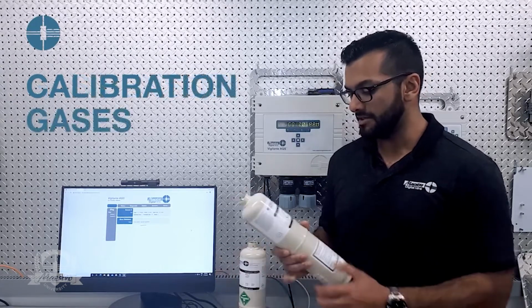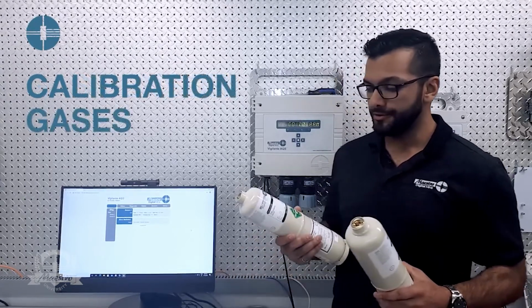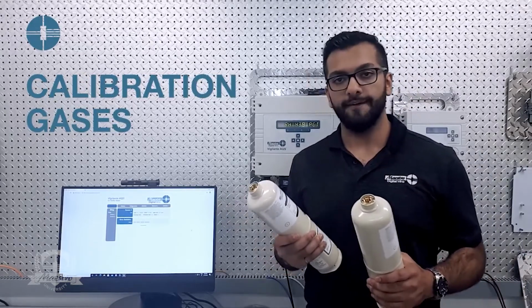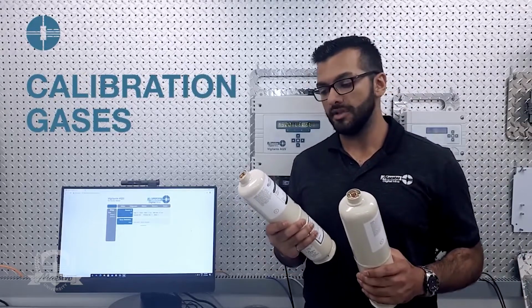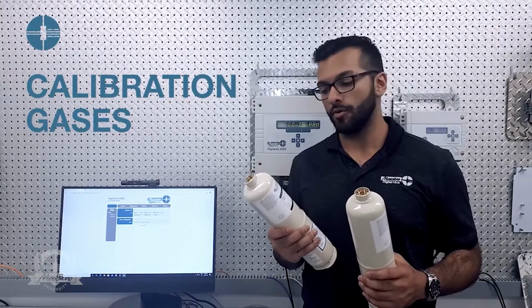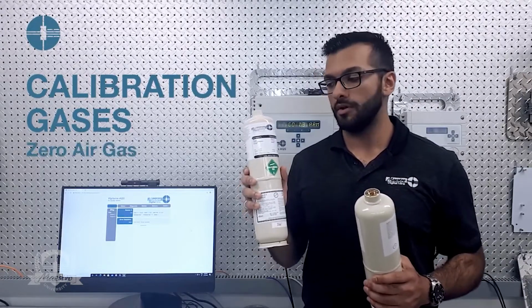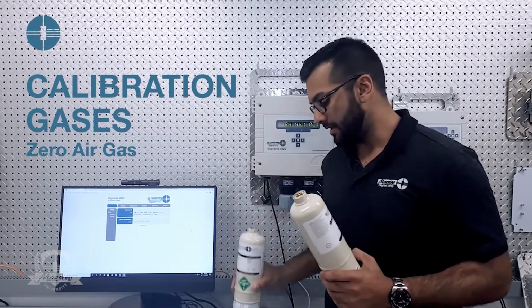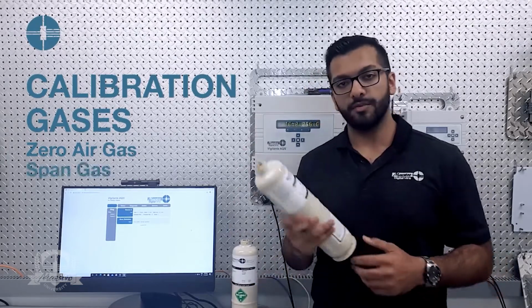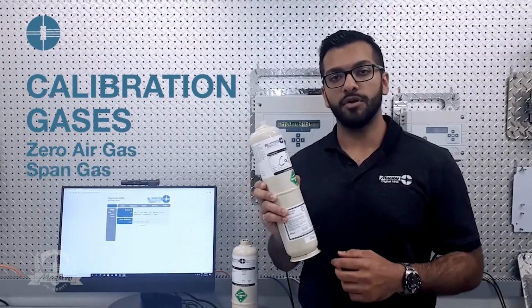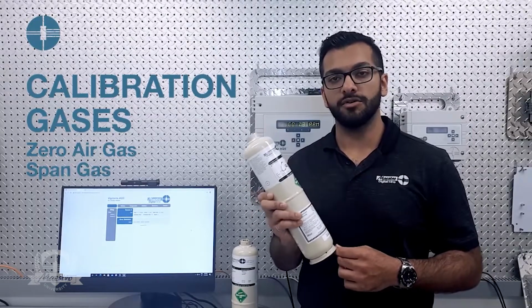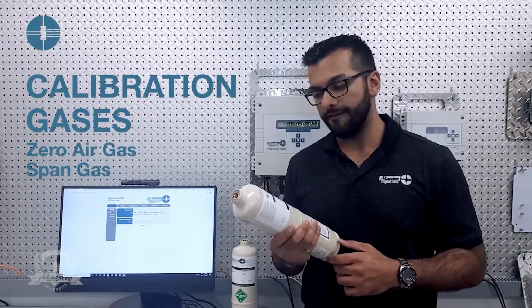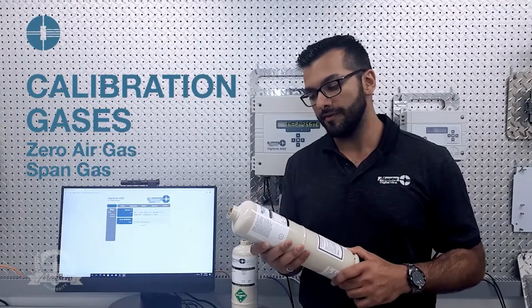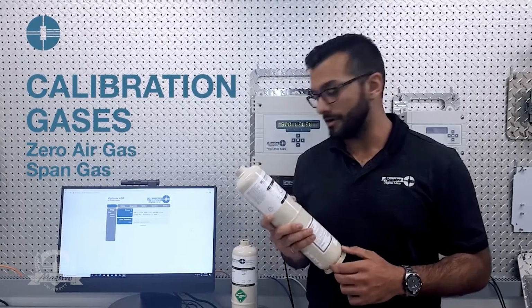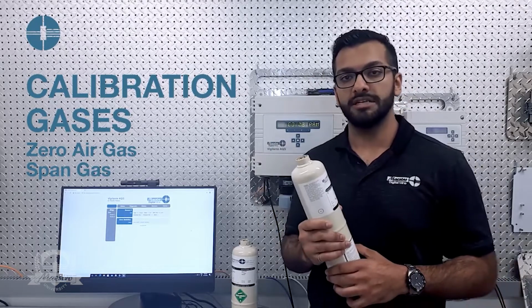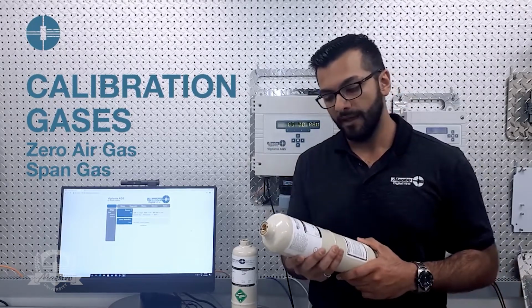Next thing on our checklist is the calibration gases. For our sensors, you'll have 2 calibration gases that are required. One is the zero gas, which will always come in a bottle like this. And the other one is the span calibration gas, which is a different bottle based on if it's a toxic or non-toxic gas. So here we have carbon monoxide CO 50 ppm, which is used to calibrate our CO 100 ppm sensor that's plugged into the Vigilante station right now.